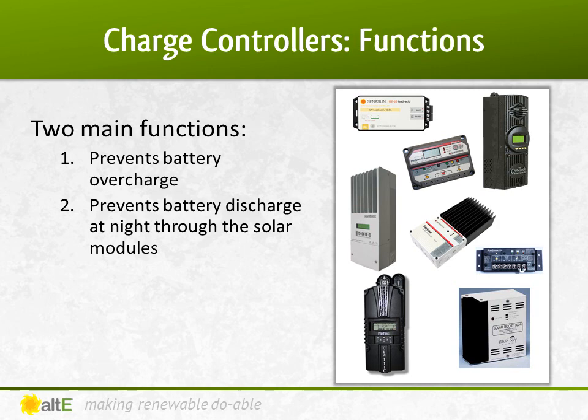A charge controller is an important component in a battery-based system. They're not used in straight grid-tied systems, as they don't have batteries to charge. Their primary role is to manage charging the battery bank — it prevents it from overcharging, and many of them control the current and voltage at which it charges. At night, the voltage of the battery bank is higher than that of the array it is connected to. Without a charge controller, the tendency would be for current to flow out of the battery bank. A charge controller prevents that, allowing the flow to only go one way into the batteries.